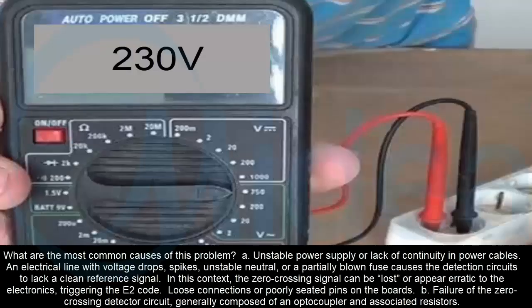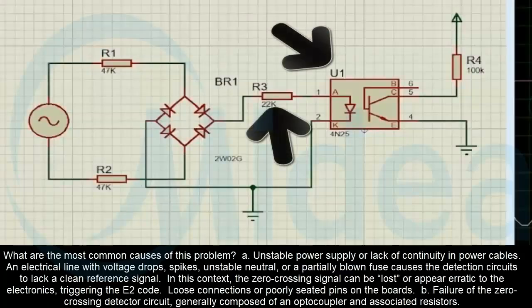A. Unstable power supply or lack of continuity in power cables. An electrical line with voltage drops, spikes, unstable neutral, or a partially blown fuse causes the detection circuits to lack a clean reference signal. In this context, the zero crossing signal can be lost or appear erratic to the electronics, triggering the E2 code. Loose connections or poorly seated pins on the boards.